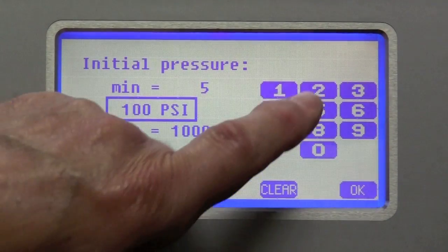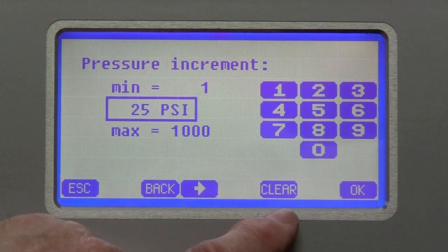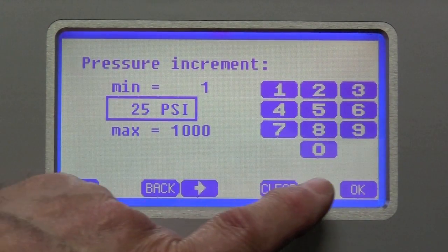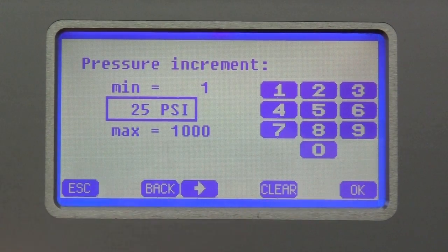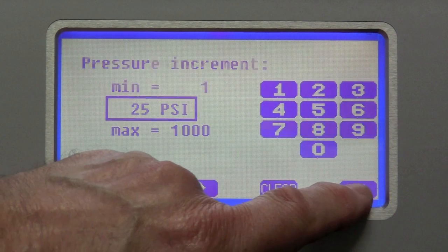The initial pressure, in this case, we're going to make it 25. I'm going to say okay. And I'm going to let it increment up 25. So that means the first step will be 25 and the next step will be 50. So we'll say okay.